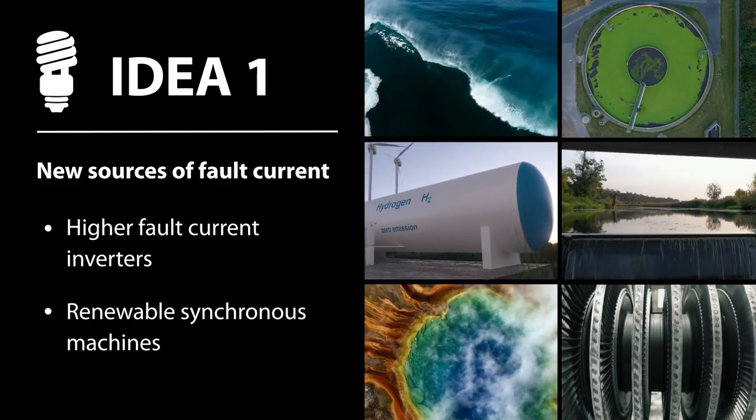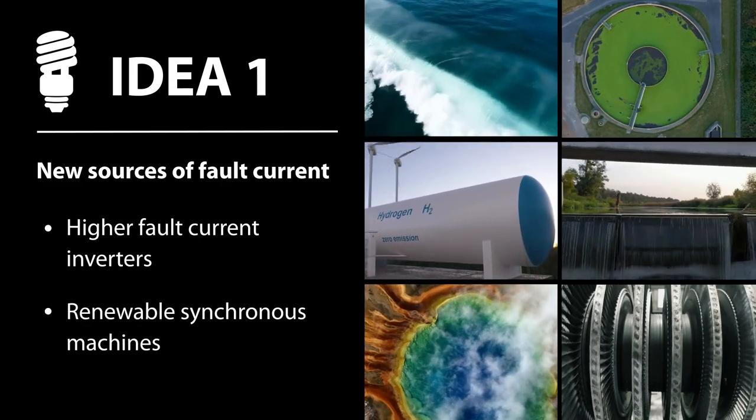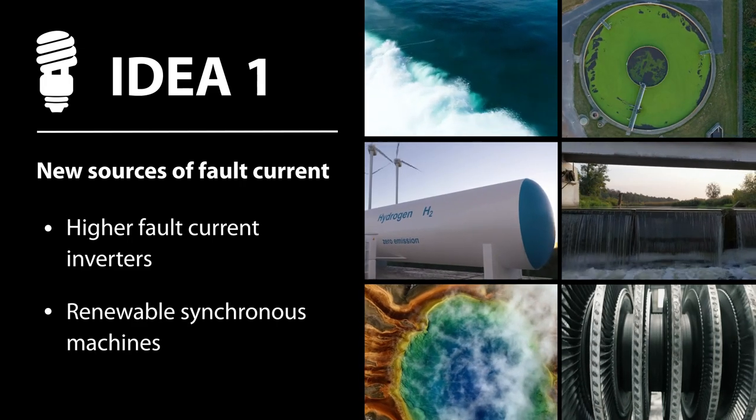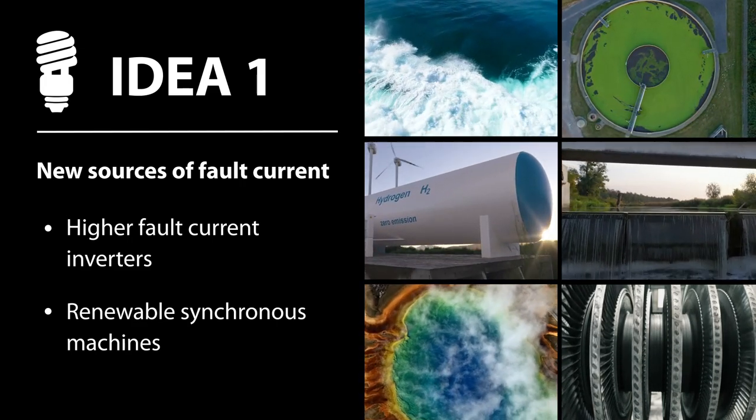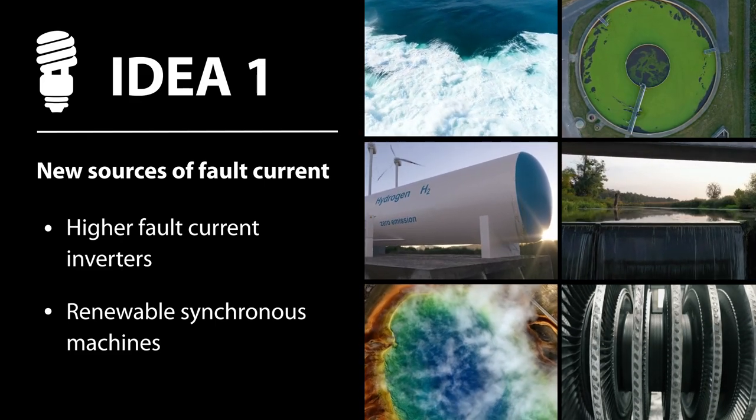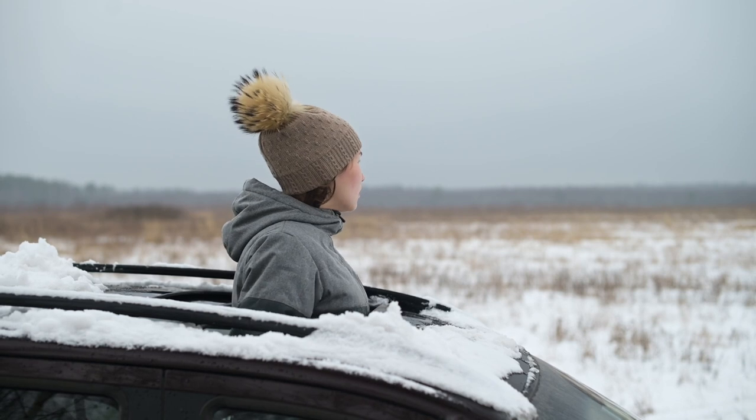Another is to continue to rely on synchronous machines that automatically inject fault current, just not the fossil-fueled ones. This could mean adding more renewable resources that use synchronous generators, including hydro, geothermal, concentrating solar power, and biofueled power plants. But these renewable resources may not exist in all the locations where we need fault protection.